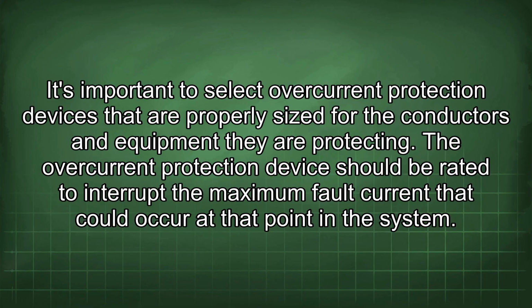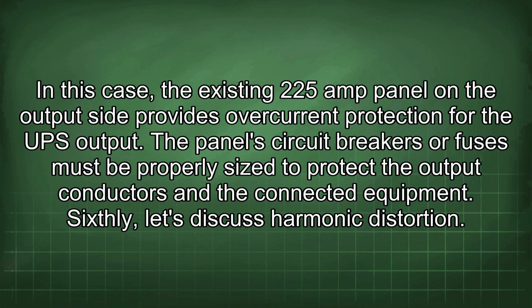The overcurrent protection device should be rated to interrupt the maximum fault current that could occur at that point in the system. In this case, the existing 225 amp panel on the output side provides overcurrent protection for the UPS output. The panel's circuit breakers or fuses must be properly sized to protect the output conductors and the connected equipment.